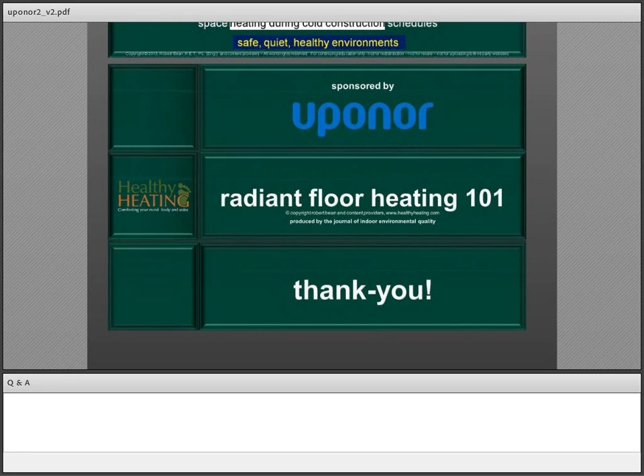But getting the system up to temperature, that's what it sounds like you guys were talking about—that's thermal lag. That lag is a function of a bunch of things: tube spacing, how deep the tubes are in the floor, how thick the slab is, and then the downward loss and the load on the building at the time of startup.